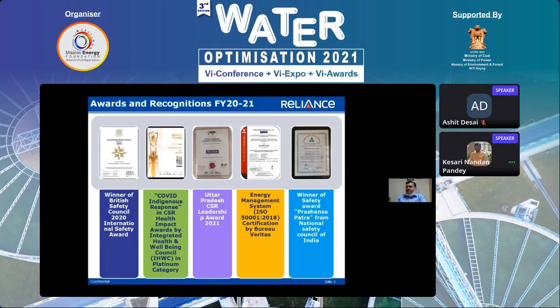So we are maintaining the best specific water consumption of 2.10 meter cube per megawatt hour, against our design of 2.45 and against the allowed Government of India guideline norm of 3.5 meter cube per megawatt hour. It is much below that. In turn, in the year 2020-21, we have saved water usage for 1.2 lakh persons, at 200 liters per capita consumption, by adopting various optimization measures. Against the design of 2.45, we have saved water for around 52,000 persons in a year, since we have maintained our specific water consumption of 2.10.